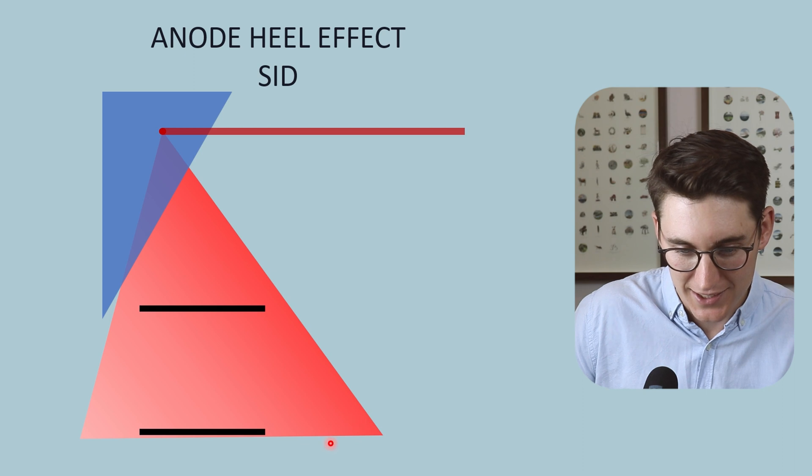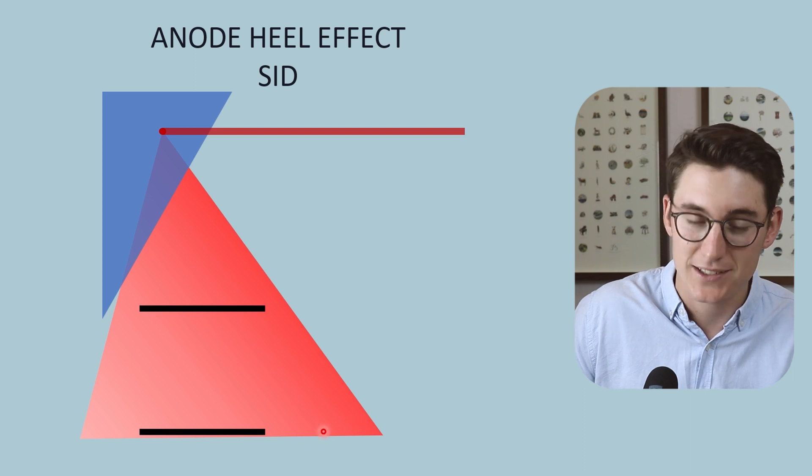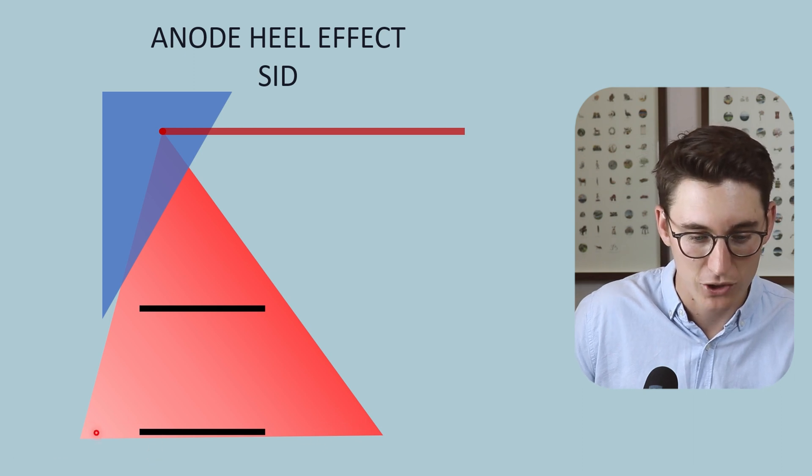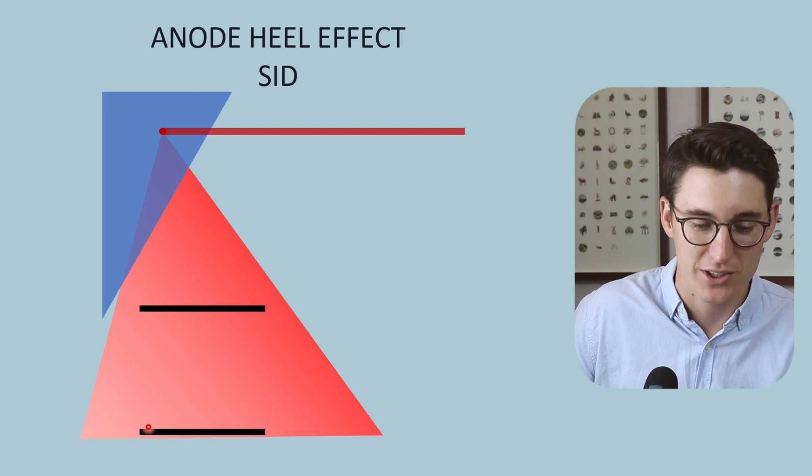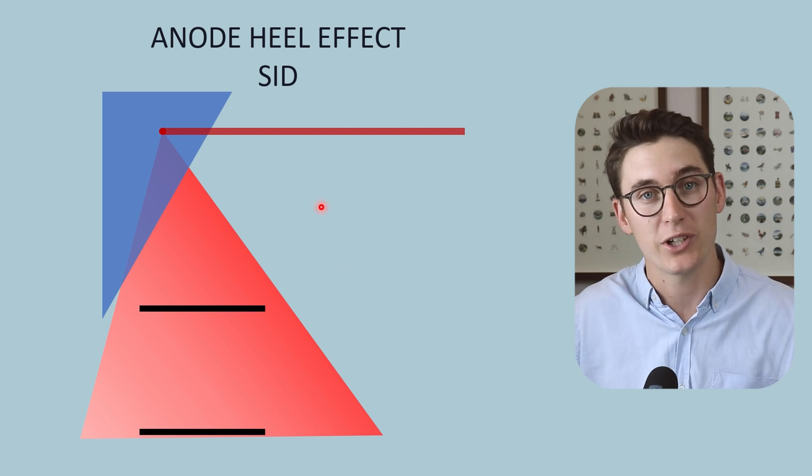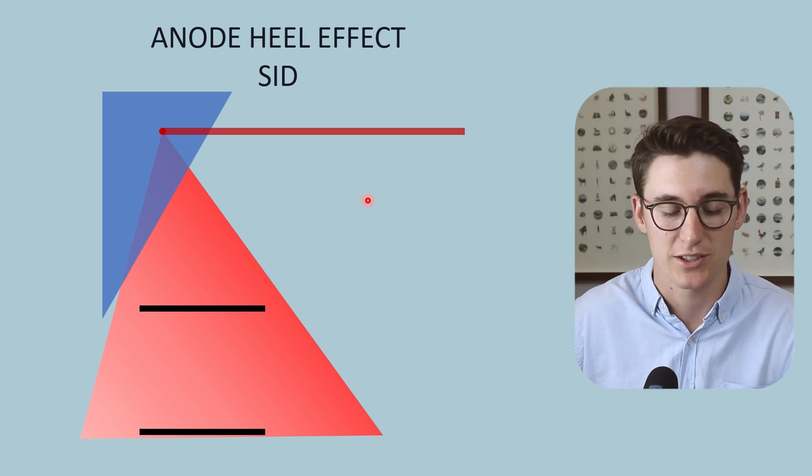That variation between this end of our detector and this end of our detector is now less. We are not getting these high energy or high intensity x-rays here and we've lost some of these low intensity x-rays here. That variation is less. We've reduced our anode heel effect by increasing our source to image distance.